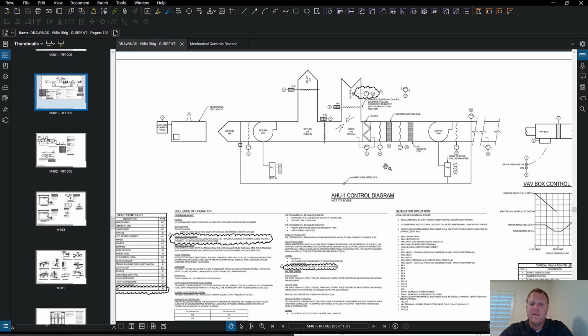So there's no load. Now think through that for a second with me here. We have a boiler. Do we need the boiler started before or after this air handler? Well, I'm going to make the argument that the air handler needs to be running and be able to blow air, and then we need to start the boiler up. But we need to flush, test, fill, and condition the piping concurrently with the air handler being worked on, so that when we're ready to start this air handler up and then start the boiler, the point being we need a load on the boiler in order for it to be fully started and work and tuned. So think of load as well.